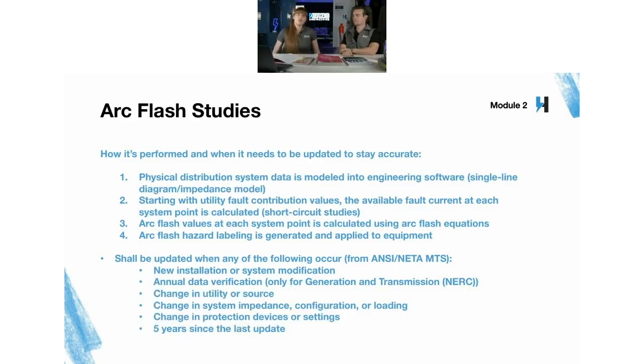So how do you perform an incident energy analysis? Well, that physical distribution system information gets put into a one-line diagram using engineering software. Starting with the one-line diagram, we oftentimes use SKM Power Tools. We've also gotten into EasyPower. Whatever you're comfortable with, that's where you put it. And that's going to be a lot of your impedance components and your overcurrent protection.